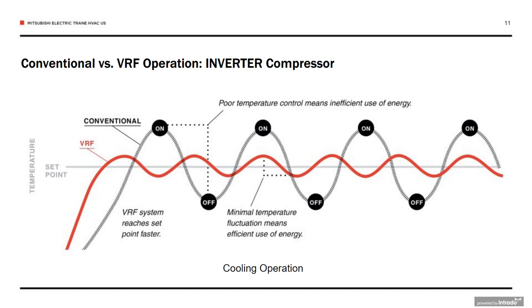Now let's look at the VRF compressor, which can go from off at the beginning here to set point really quickly by ramping up. In this case, it varies its hertz to get to set point quickly and will modulate throughout the day. It will not turn off. It will just hover around that set point to deliver the cooling and temperature adjustments that you need throughout the day as people come and go out of a conference room or as tenants come and go out of their office spaces. Now, this allows for quick response to that temperature change. This also gives you some added benefits of continuously filtering the air in the space and keeping the air from becoming stagnant. Very important during this current climate.